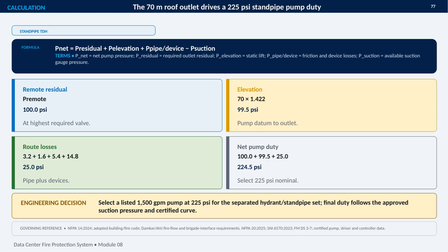This calculation establishes the standpipe total dynamic head, or TDH, required at the pump. The governing point is the highest required valve, where the system must maintain a remote residual pressure of 100 psi. Next, we account for elevation. The 70-meter vertical lift is converted using 1.422 psi per meter, producing 99.5 psi from the pump datum to the outlet. Route losses through the pipe and devices add another 25 psi, made up of the listed component losses: 3.2, 1.6, 5.4, and 14.8 psi.